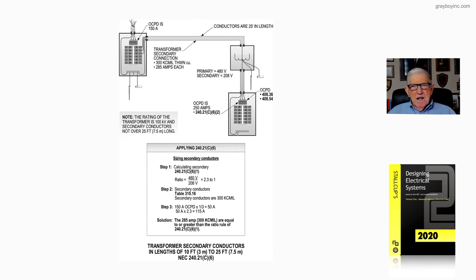Now, we take 50 amp times the ratio of 2.3. We come up with 115. We have to be equivalent to that or larger. So we have 285 amps, 300 kcmil THWN are equal to or greater than the ratio of 240.21C6 item one.